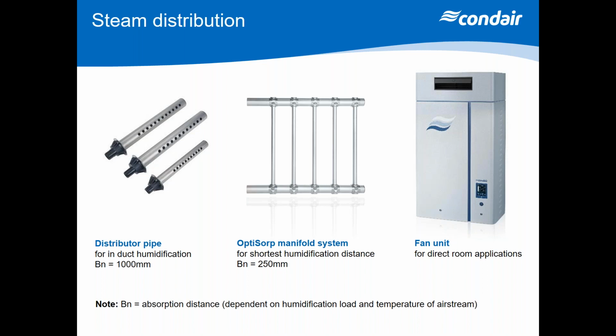But we need to think about whether there's anything else happening after that distance, because if there's a HEPA filter, I need 2.5 times that distance. Well, all of a sudden, we may have a very long section requirement, and that may not always be possible. When we are faced with that scenario, we use a short absorption distance manifold. Basically, we're putting lots of tubes in the airflow with lots of holes and introducing steam across the whole cross-section of the duct or air handling unit. By doing that, we reduce that distance. Now, we may not have a ductwork or air handling unit to put air into. It may just be something like a comms room or a switch room. And for something like that, we can just use a fan unit for direct room applications, where we're going to blow a small amount of steam directly into the space. So how we get the steam into the duct or into the space needs some evaluating as well.